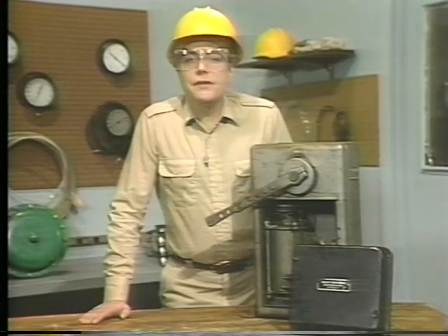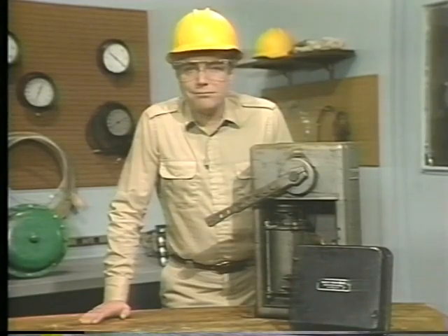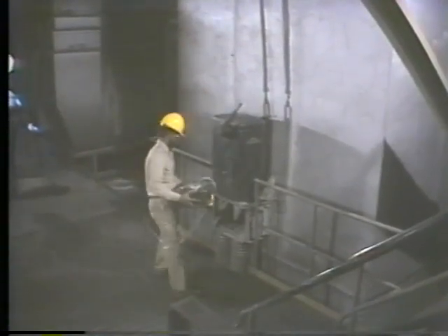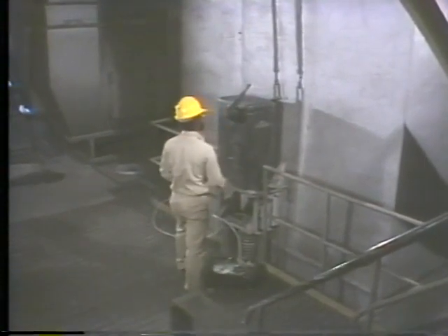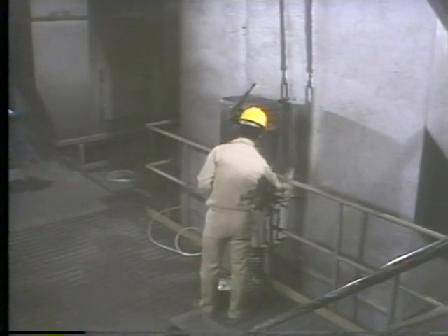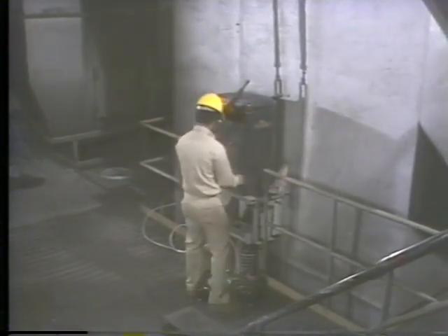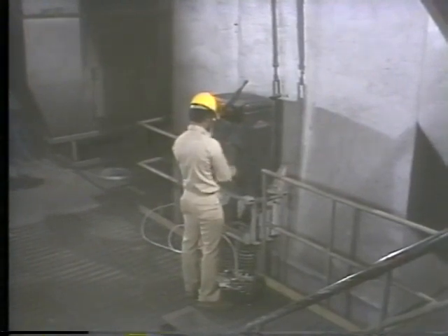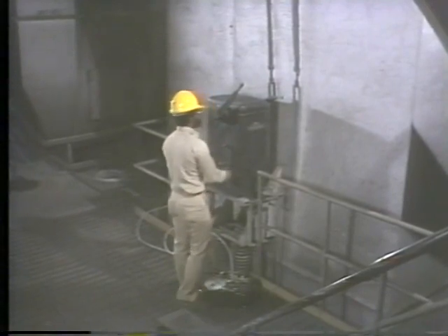Later, we'll observe as he adjusts the same kind of positioner with a diaphragm actuator. The actuator and positioner in this application is used to position louvers that regulate the flow of air through a large duct. The duct isn't carrying any air right now because it's been taken offline and shut off from other systems. This way, the technician can make adjustments without affecting other processes down the line.